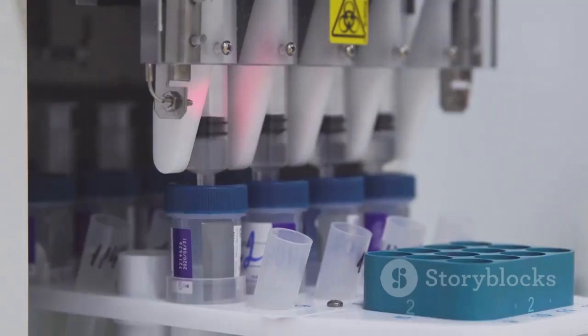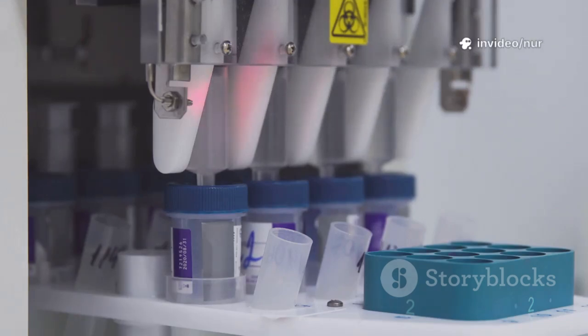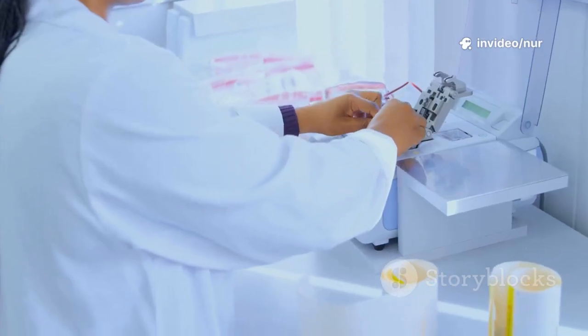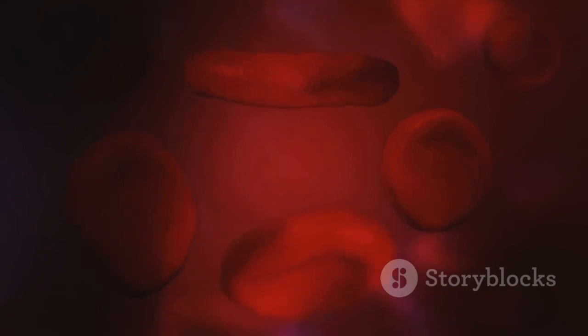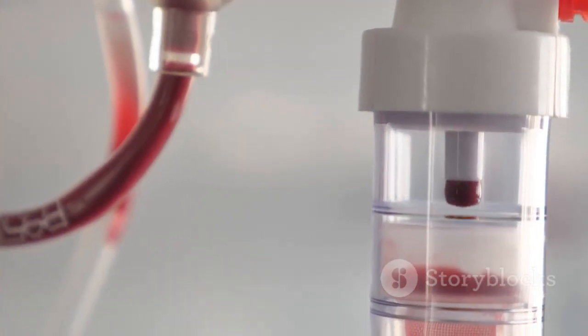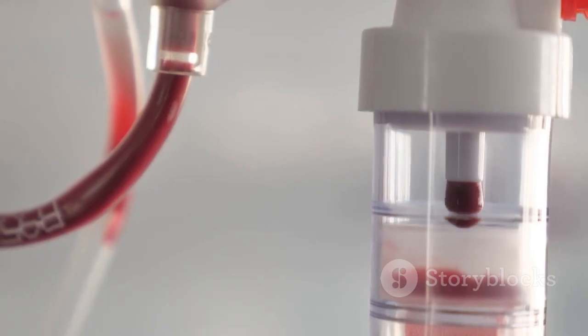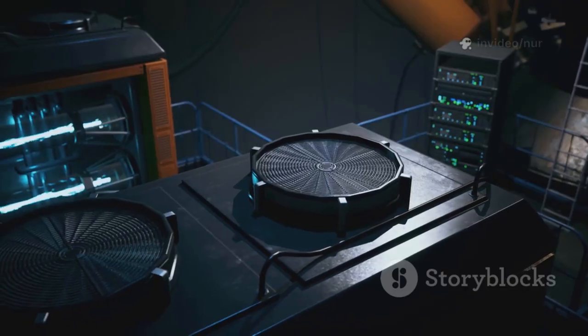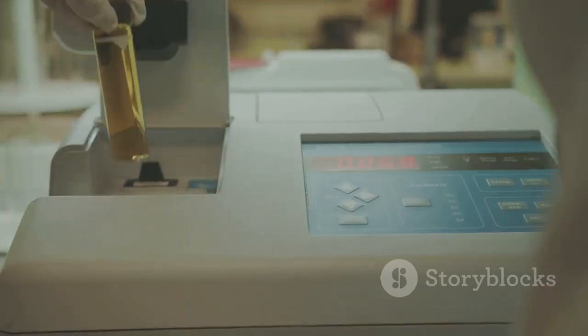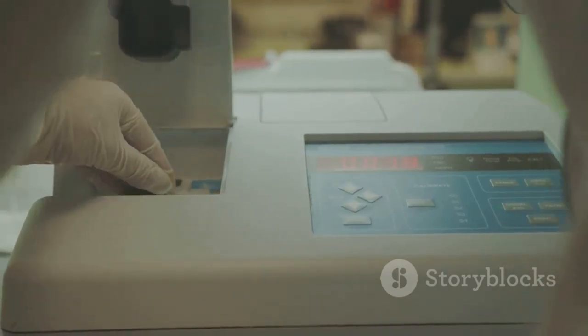So how does this amazing machine count millions of cells it can't even see? It uses some very clever technology. One common method is called electrical impedance. The blood sample is diluted and then pulled through a tiny hole called an aperture. An electrical current is flowing across this aperture. Since blood cells don't conduct electricity very well, every time a single cell passes through the hole, it briefly interrupts the current. The machine counts each one of these interruptions as one cell.